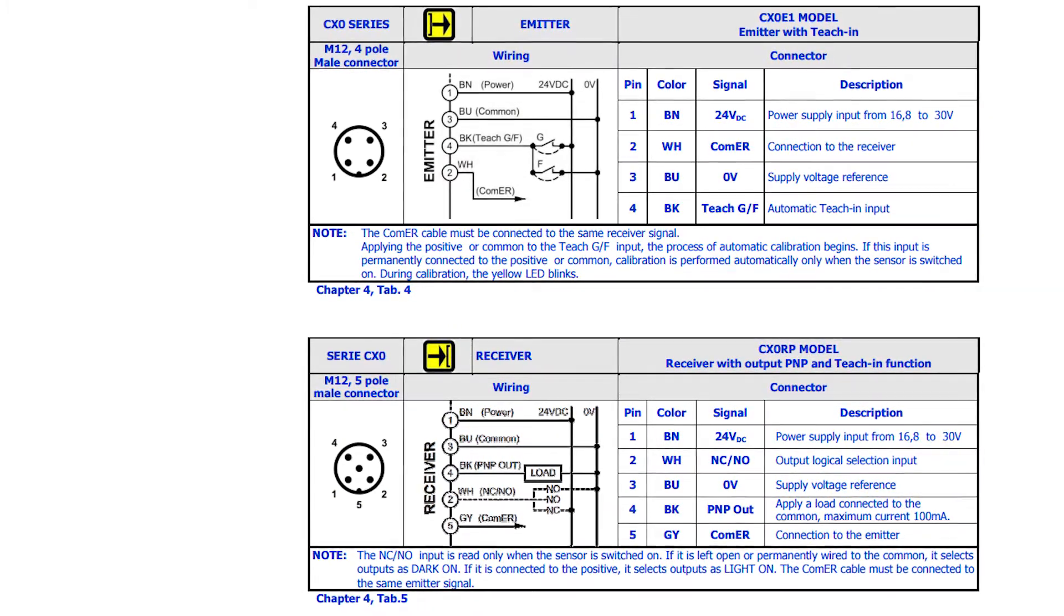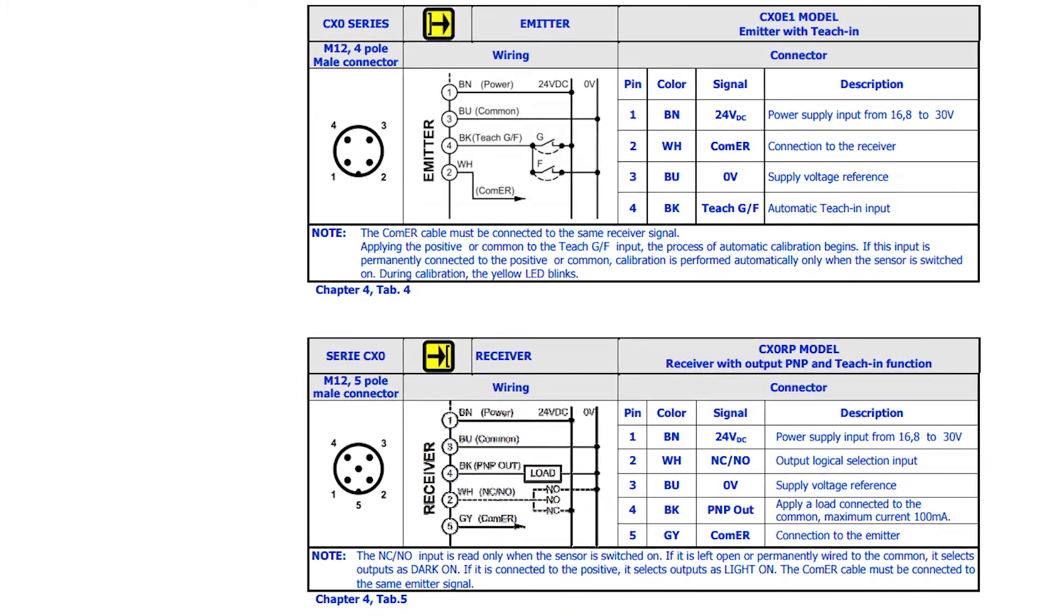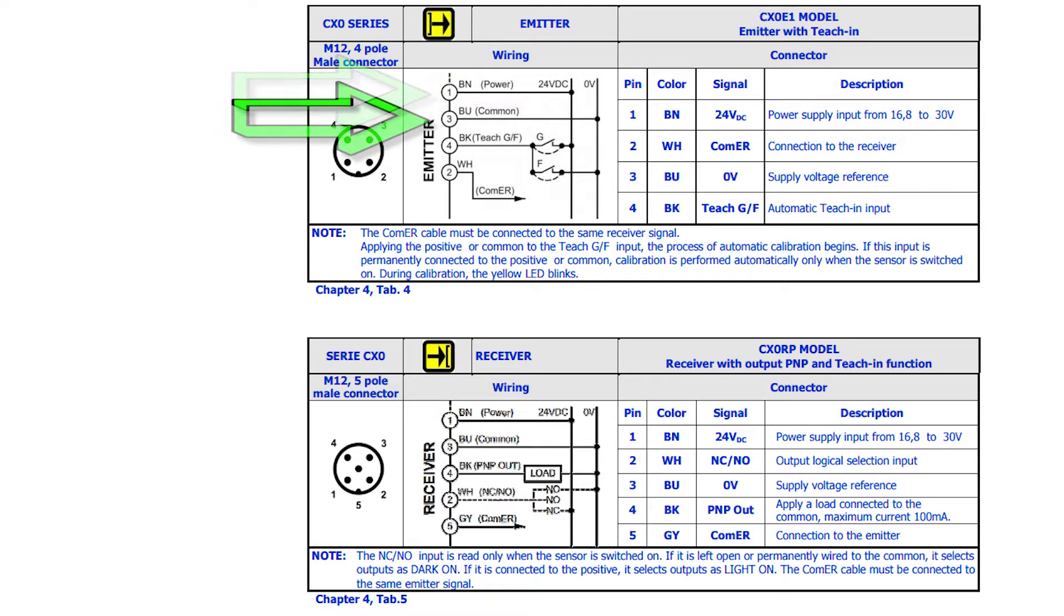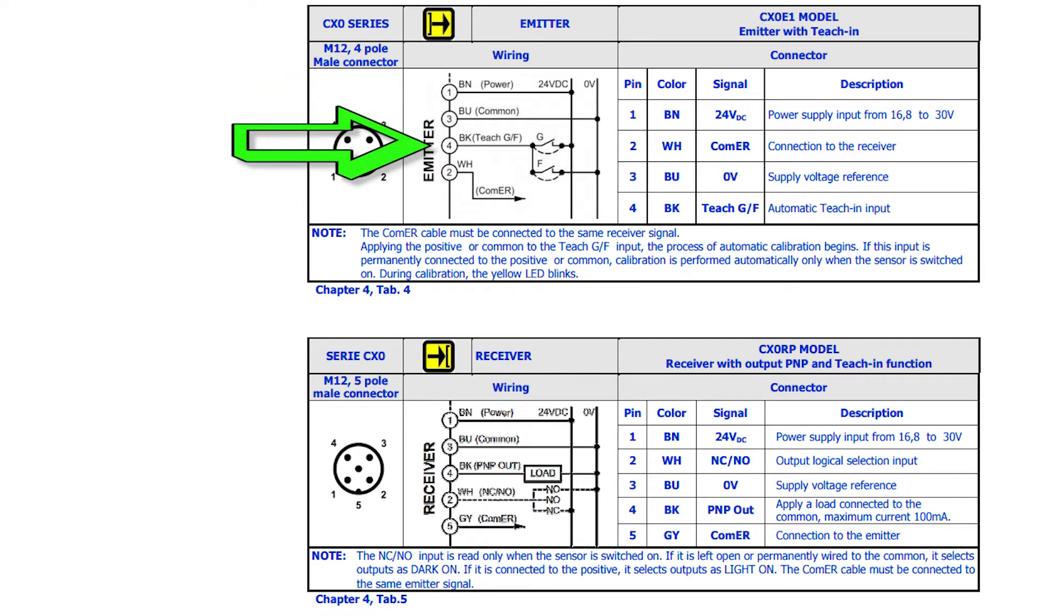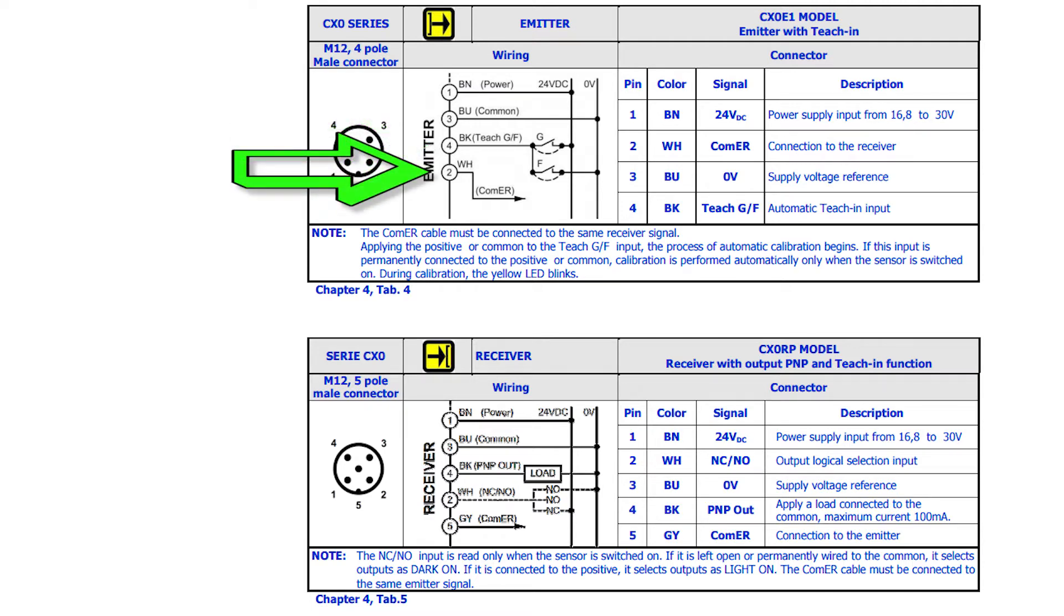The emitter has 4 connections: brown for positive voltage and blue for negative voltage or common to power the sensor. Black should be connected to a switcher device to allow for gross or fine teach functions. Last, white should be connected to the gray wire on the receiver.